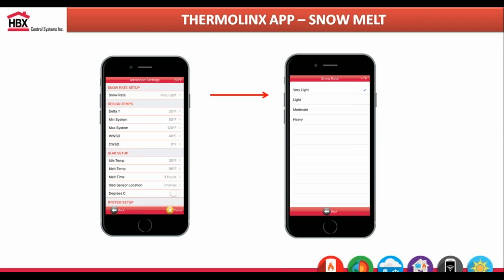So if they ever were to give them a call, they can just log into their system, change a couple of different parameters, hit save, and that's it, not actually having to go to site just to do the exact same thing. Typically, 9 out of 10 times, it's just a settings issue in terms of troubleshooting. Maybe their slab didn't melt all the time, so maybe they just have to add another hour of melt time operation, or maybe they just have to increase their system temperature a little bit, and usually that'll solve the problem.